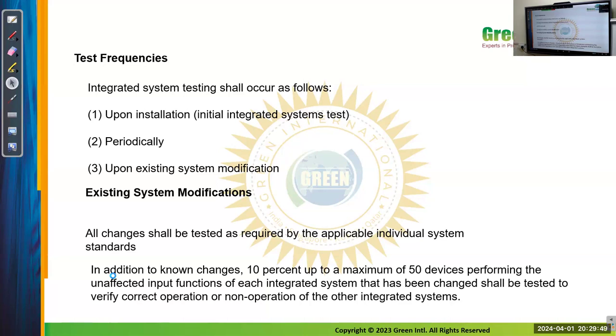For existing system modifications, all changes shall be tested as required by the applicable individual system standards. In addition to the changes, 10% up to a maximum of 50 devices performing the unaffected input functions of each integrated system that has been changed shall be tested to verify correct operation or non-operation of the other integrated systems. That is, 10% or up to 50 devices: if we change devices in a system, then we have to perform the integrated testing.